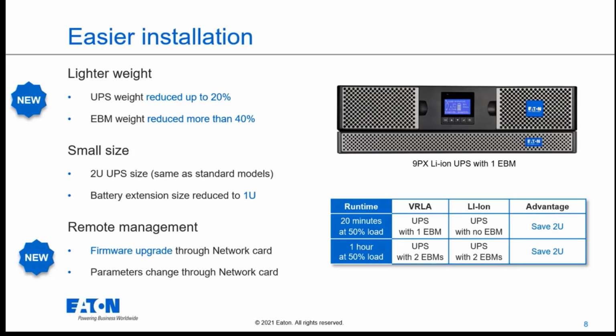Of course, the lithium-ion also brings advantages on the installation side, because obviously the lithium-ion cells are lighter than normal VRLA. This allows us to reduce the weight of the UPS by up to 20%, and the EBM weight has been reduced by more than 40%. And of course, if you have a lighter UPS and a lighter EBM, it's easier to install them in a rack, which is obviously the most common installation for this kind of UPS. We have kept the same size for the UPS, so it's 2U. The picture that you see on the right part of the screen represents a UPS plus one EBM. So it's not a solution with only the UPS, it's UPS with EBM. And we have been able to keep the 2U size same as the standard model.